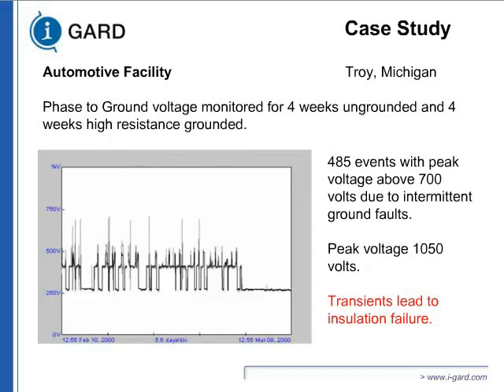120 times a second, it is giving a high voltage pulse, and eventually the insulation will fail. Insulation cannot stand that. Common practice used to be to use higher voltage insulation, but that can only delay the failure. It cannot eliminate it. And look at that sketch you have: 485 events with over 700 volts. If a 480 volt system is getting 700 volt peaks, what can happen to the insulation?